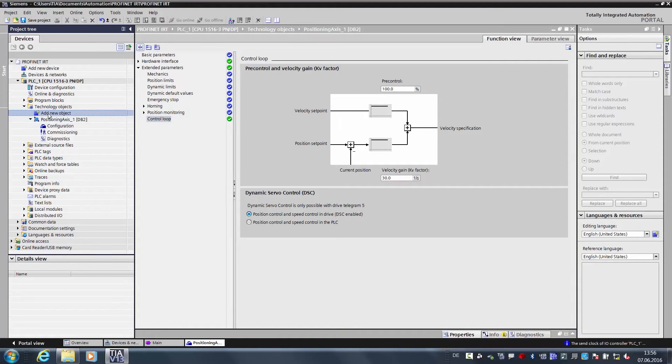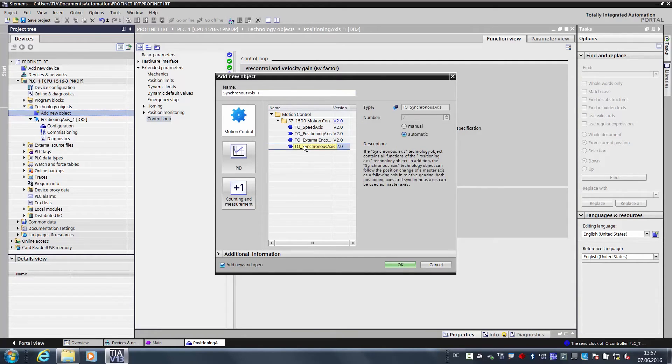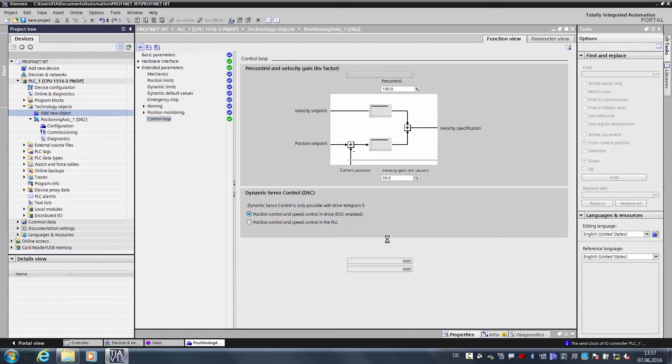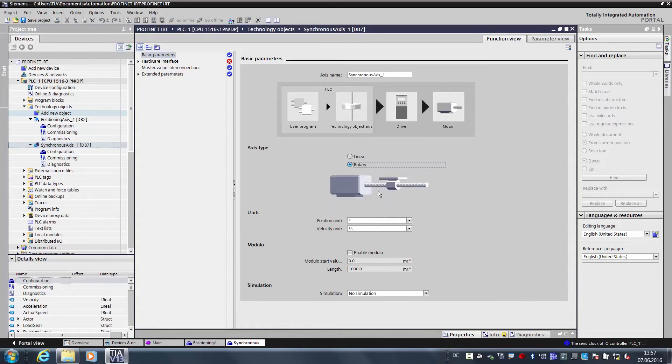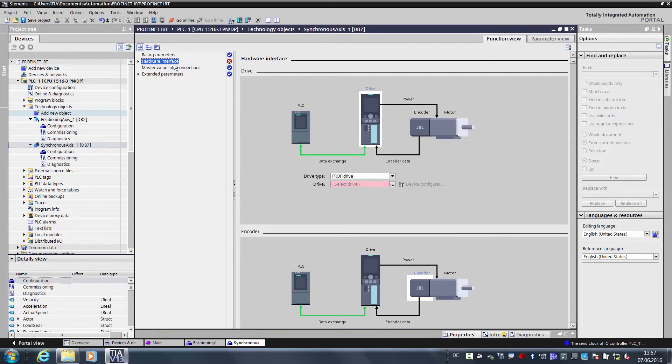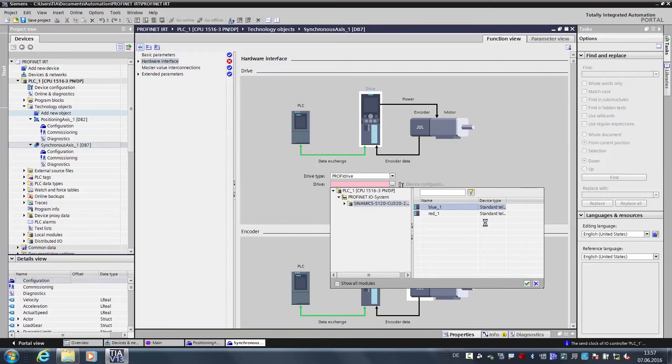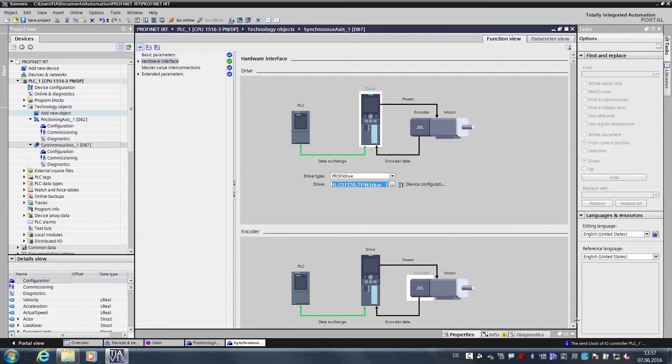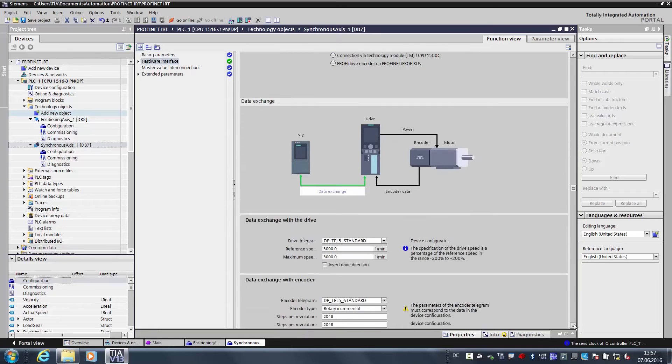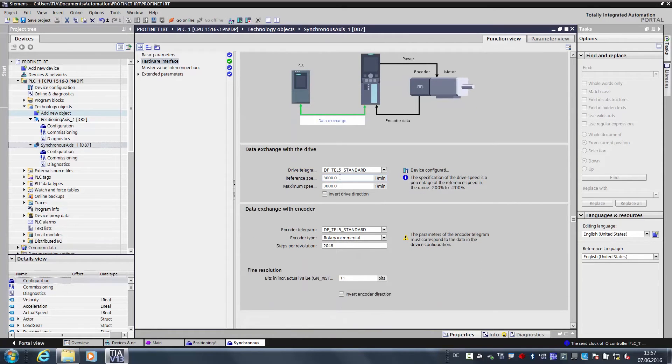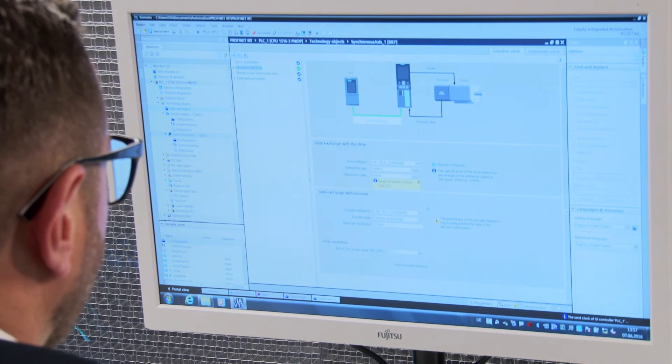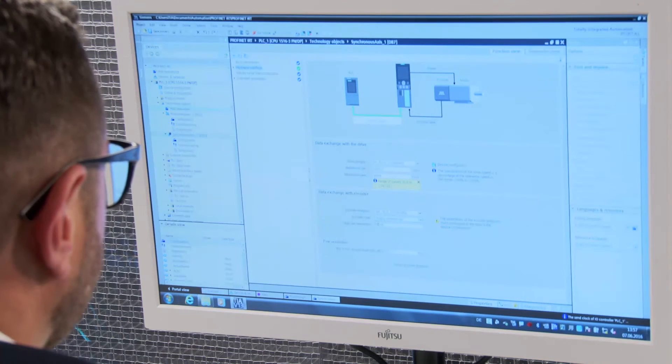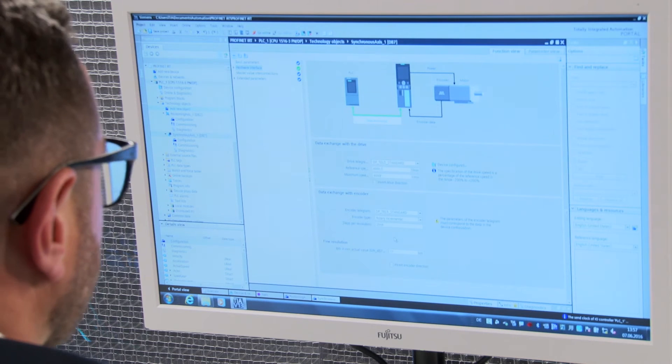And now we add a second axis, creating a new technology object for this purpose, also a motion control object and here a synchronous axis. As with the first axis, here we also have a rotational axis, and we need to define the hardware interface for this one as well. Here we also use the PROFIDRIVE TELEGRAM. And then select the axis, which in this case is the blue axis, the slave axis in our system. We then move down to the data exchange and the TELEGRAM 5 remains the same as with the first axis. Reference values are also 6000 rpm. And here the sensor is already properly set up, because here we are using a rotational sensor with 2048 increments.